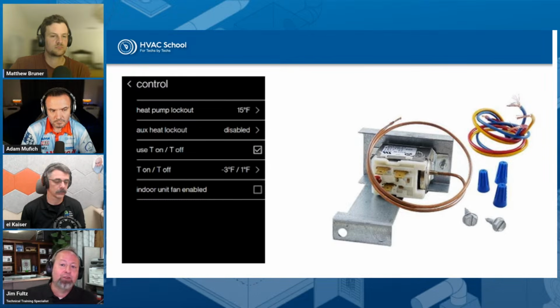So you need to run that second circuit, that second wire, to the outdoor unit for that thermostat to be able to cycle that resistance heat on, rather than turning it on and losing the efficiency of what you could be getting out of the heat pump by not letting it run continuously.